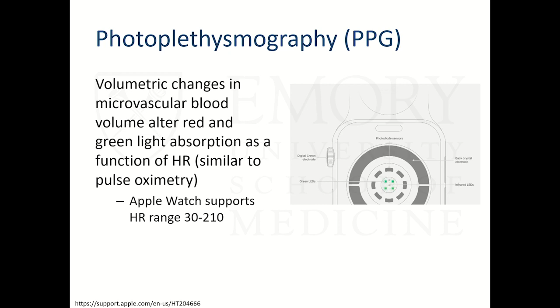They don't really present any data, but Apple says that the algorithm they use for red and green light photoplethysmography can detect heart rate relatively accurately, not necessarily AFib, just heart rate, over a dynamic range from about 30 beats per minute up to about 210 beats per minute. So it's relatively robust in that regard. And they don't really talk about their specific algorithm, but in essence, the way the PPG works is you can imagine that using the absorption of red and green light, you can get something that looks like a pulse oximetry tracing. And you can use both the amplitude and the irregularity of the pulse interval to develop an algorithm to try to detect atrial fibrillation.